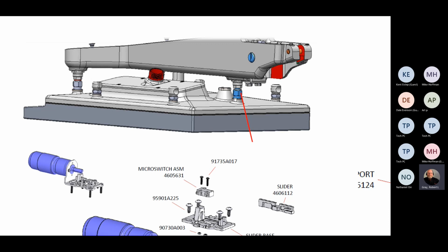Okay, if you over crank it on the bottom part, you will snap this inside the platen, and then you're probably going to end up replacing the platen if you can't use an easy out to get that out of the platen. Either way, you don't want to put all your strength into tightening that. Okay, if you see threads showing, reverse it a little bit because somebody was in there, and put the blue Loctite on it, because if you don't do that, what's going to end up happening 3 to 5 months later, you're going to be back out to recalibrate.